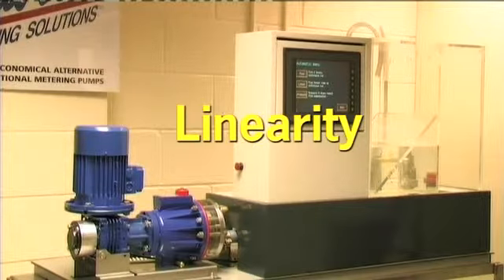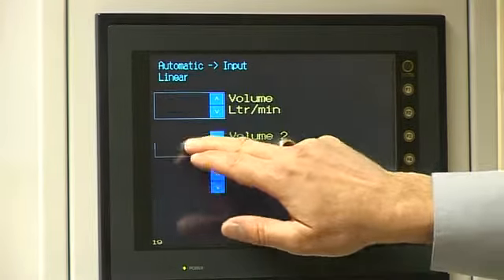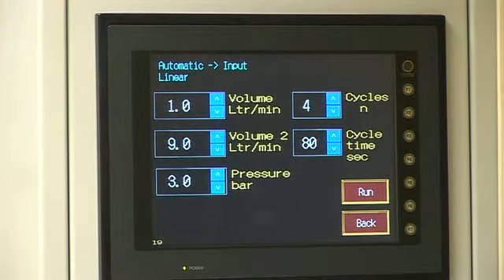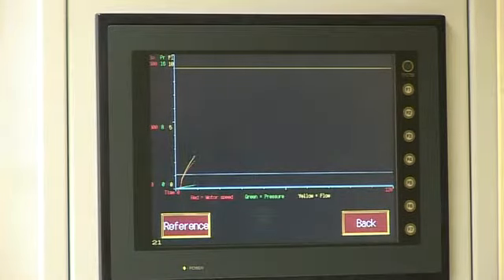The linearity performance of the Hydrocell is demonstrated by this test, whereby the VSD motor is set to increase in speed in a linear fashion, with flow rate increasing from 1 litre per minute to 9 litres per minute. 1 litre per minute is achieved by a motor speed of 50 rpm.